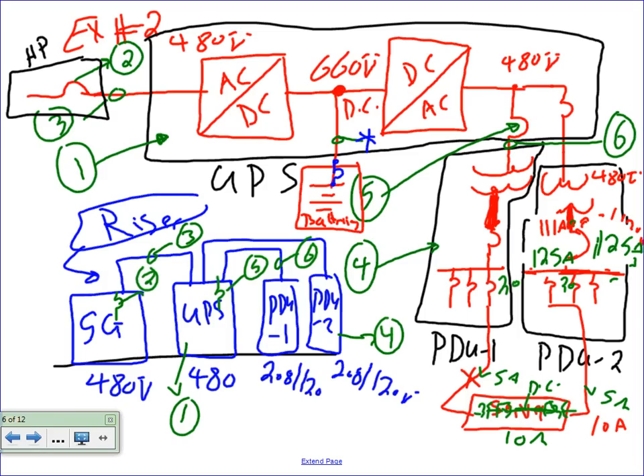So I have a 480 switchgear feeding a UPS that's 480. From the UPS, I'm feeding 480 to 208/120 PDUs. Where's the transformer, like Chris did? The transformer happens inside the PDU in real life. In our project, we dropped it outside for CAD, for Revit. What's this? It seems rather ridiculous to take, you've got AC to DC up in the very upper left-hand corner. Yeah. Your end game is to feed 2 machines.